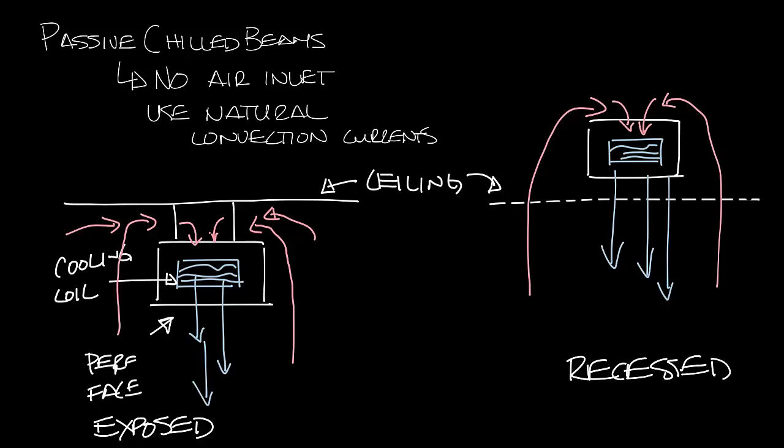Because the cold air falls directly below the passive beam, you want to make sure passive beams are located in hallways or other areas where people won't be sitting directly under them in the space.